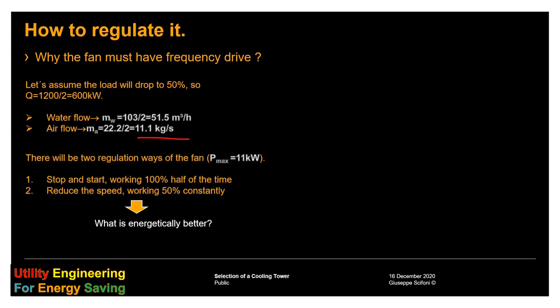There will be two regulation ways. Considering the power fan 11 kW, we can either stop and start the fan, working half of the time, but every time at 100%, or reduce the speed, working at 50% of the load, but constantly.